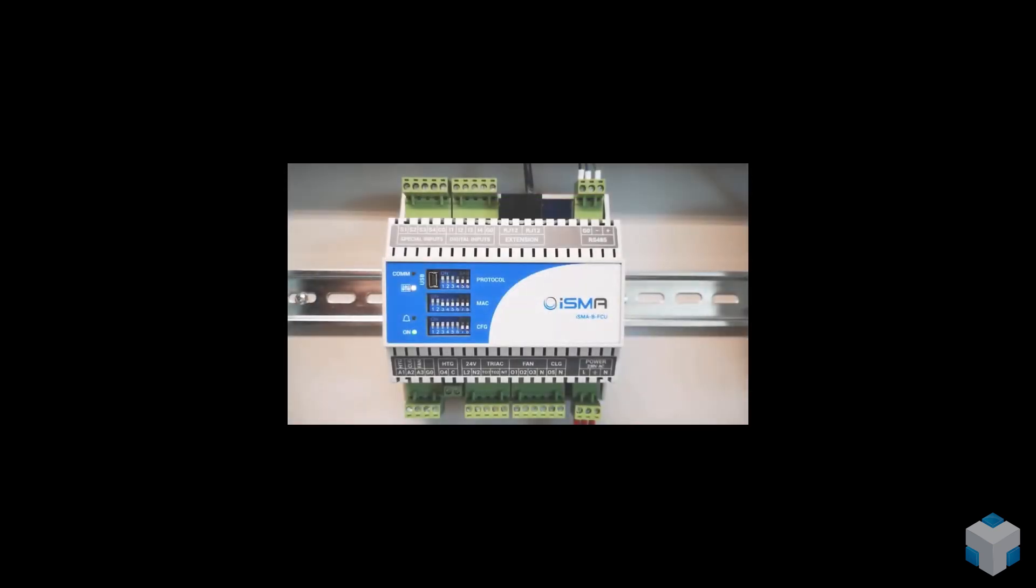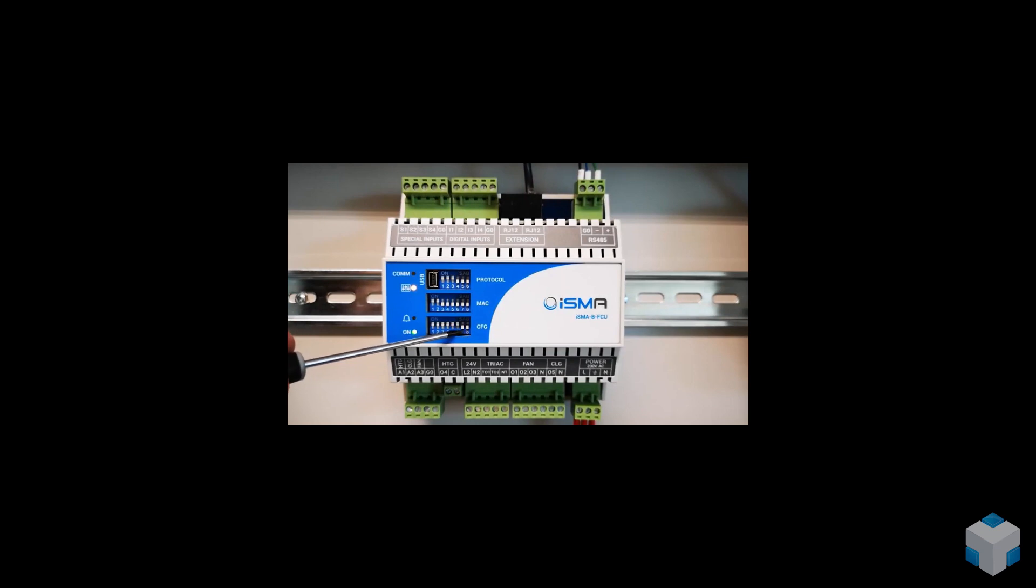The default application is designed to control one of four different fan types. Those are controlled by analog value from 0 to 10V, 1, 2 or 3 speed fan type. Configuration DIP switches number seven and eight are reserved for that fan type control selection.